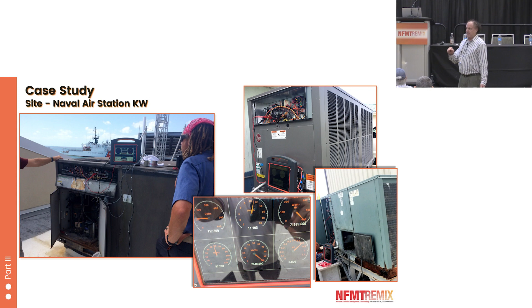And that's where the diagnostic analyzer comes in. So this is a prototype that we developed. And what it does is measure the cooling capacity or heating capacity, the power consumption, and the efficiency level. And then it has diagnostics built into it, sort of like a really basic AI, where it looks at all the different combinations of temperatures and humidities and compares them to what would be optimal in those particular conditions. And then it throws up on the screen, again, something simple: refrigerant charge low, suggested action is to adjust refrigerant charge to a subcool of 10 degrees or something.